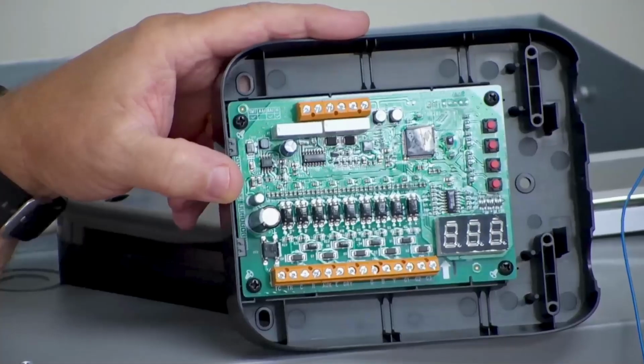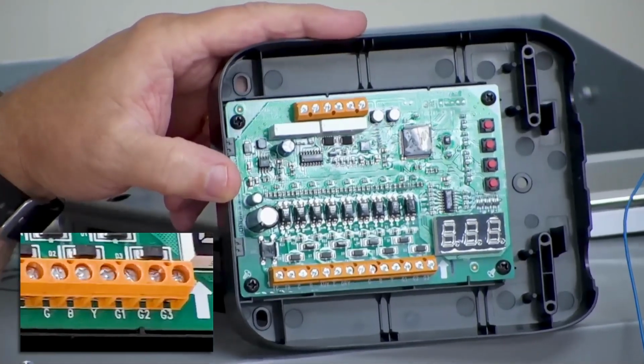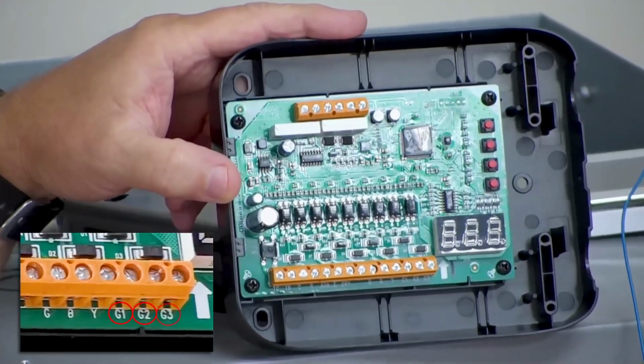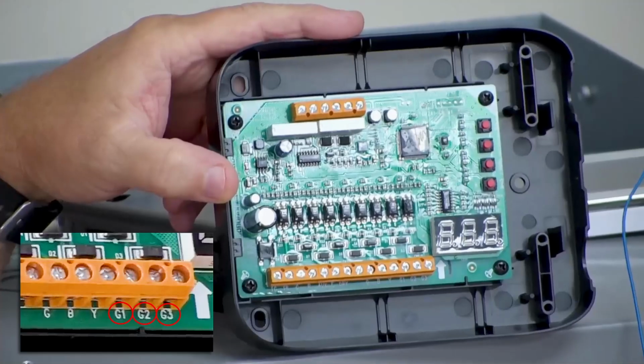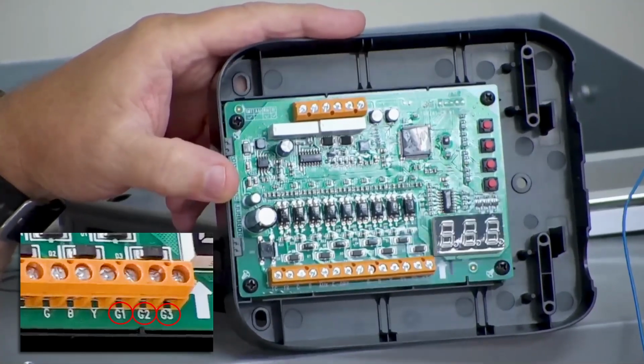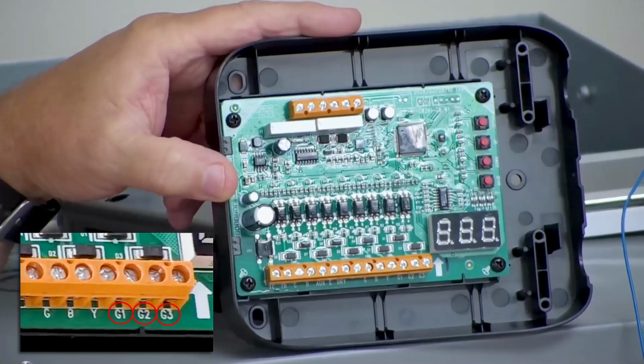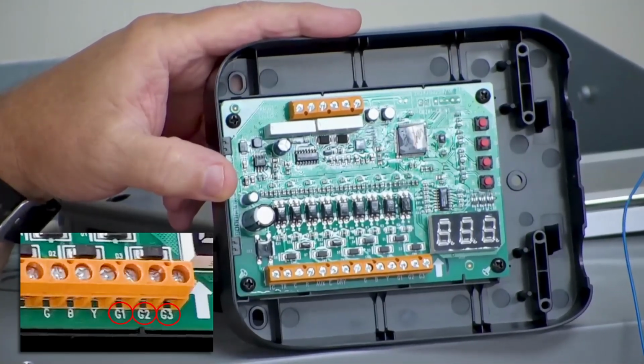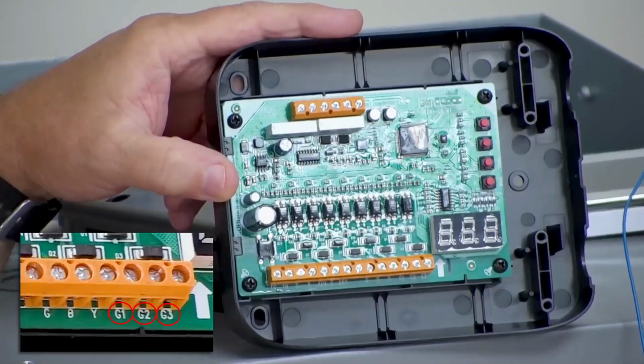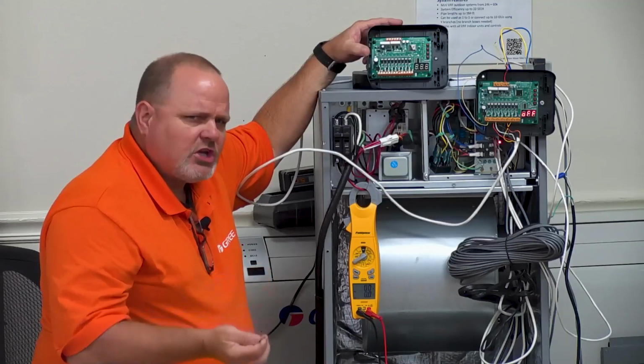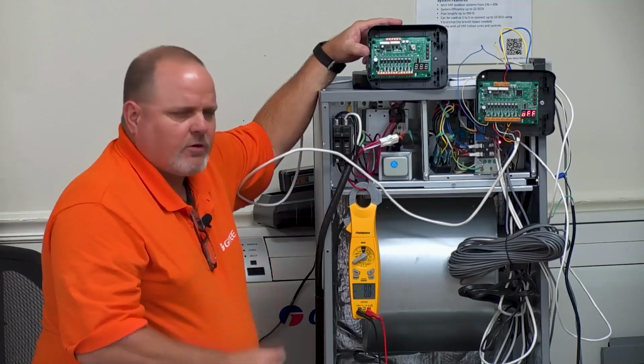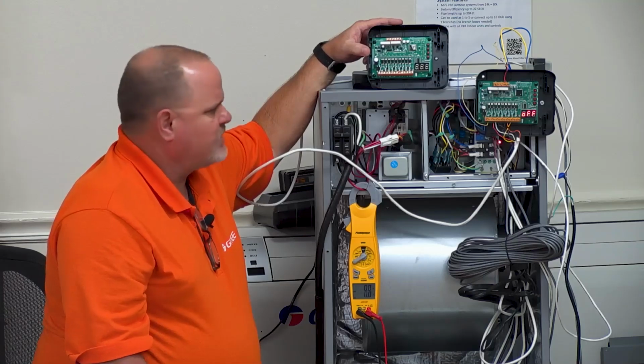If you have a thermostat that gives you the ability to have a G1, G2, and a G3, then that would be low, medium, high, respectively. So then you don't have to set the P code because it's going to be dependent on what thermostat signal you get, whether it's a G1 or G2 or a G3. Those thermostats are not real popular anymore. You don't see them a lot. So most of the thermostats you guys will be working with will just have a G terminal.